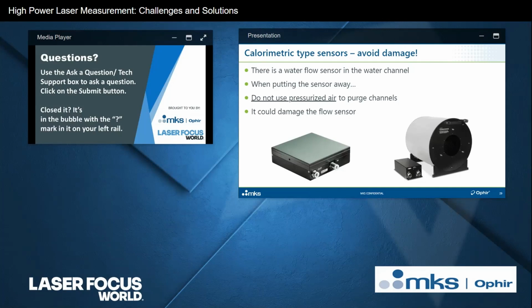When you're done with your measurement and you're putting the sensor away, obviously you're going to want to drain the water out. Otherwise, you don't want to just leave the water in there for a long time because that could lead to mineral deposit buildup as the water dries. So you're going to pour the water out, and you probably don't want to leave drops of water sitting in there, so you're going to want to purge the channels of any leftover water. Do not use, and I'm saying it as emphatically as I am because we've learned this the hard way, through a lot of bitter experience, do not use pressurized air to purge the channels of any last bits of water residue. I'm being gentle here by saying that it could damage the flow sensor. The truth is it will damage the flow sensor. Water in the sensor should only be removed by tilting and turning the sensor and letting it drip out, and there isn't really much of a shortcut.